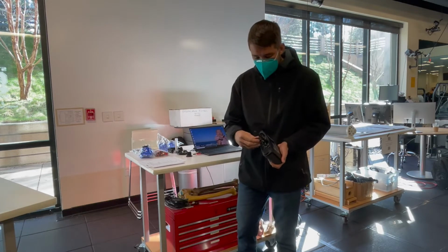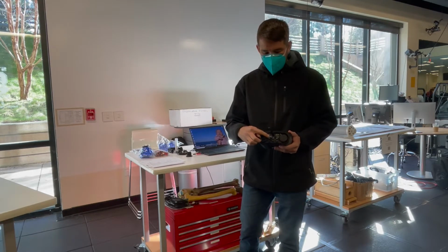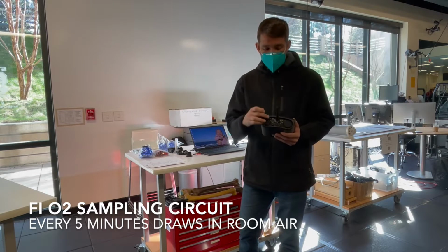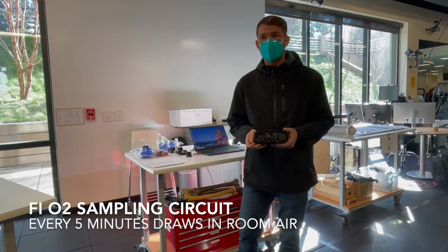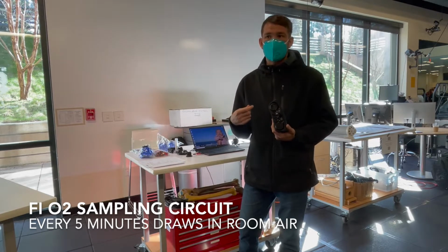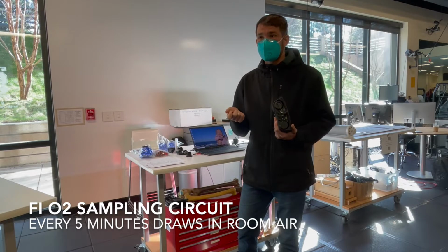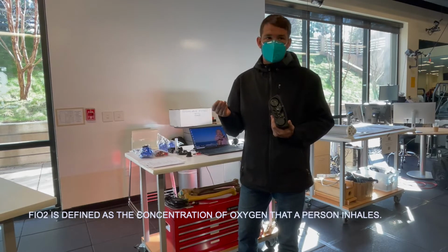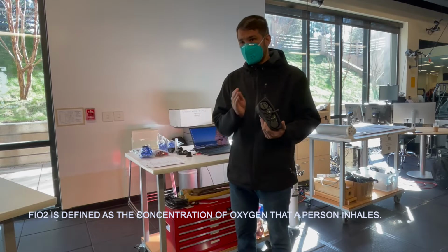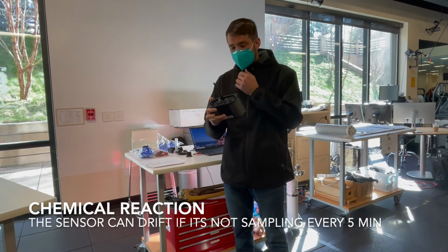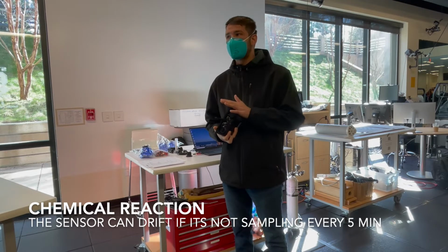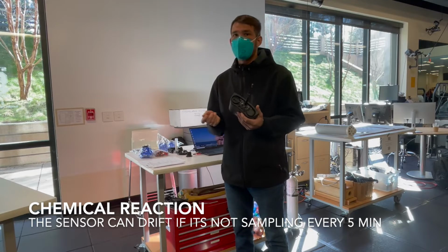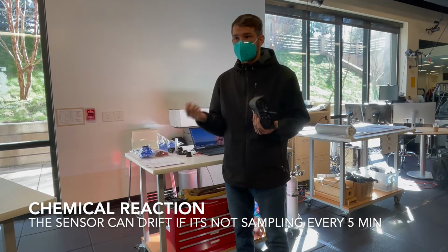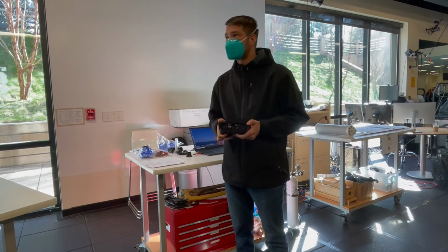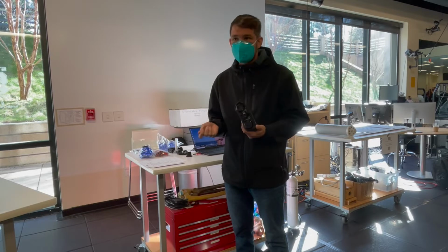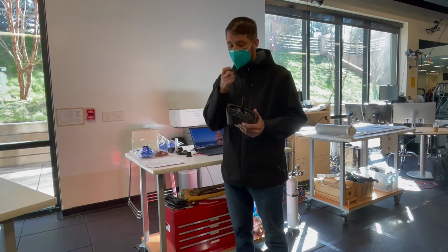And then right here, this little mushroom cap goes over our FiO2 sampling circuit. So basically what happens is every 5 minutes, when you're running a test or when it's just sitting here, it's going to draw in the room air, so that it can see whether the atmospheric CO2 or O2 is drifting. So it can reset that baseline, because this analyzer is based on a chemical reaction, not a physical reaction. So the sensor can have a tendency to drift if it didn't sample the environment every 5 minutes. It just happens in the background. You're not going to notice it happening.